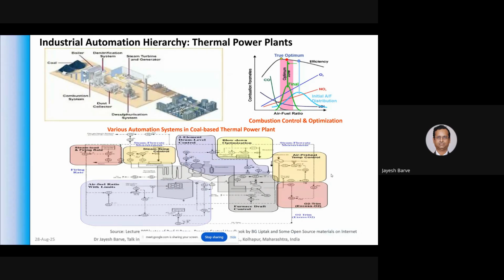If you have too much air, it's a less efficient combustion, so temperature will be low. If you have too little air, it will be incomplete combustion, so you might not fully combust it. C plus O2 with proper combustion will give you CO2, but incomplete combustion gives you CO.